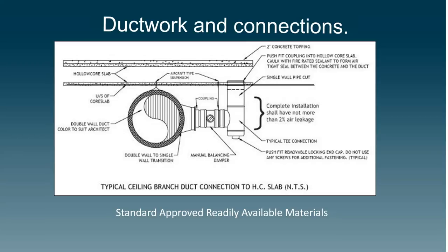Mechanical contractors and sheet metal ductwork people don't need to retool themselves — it's standard equipment. The only difference is that the ductwork is smaller, and if we use hollow-core slabs we eliminate the need for a lot of branch ductwork, so installation becomes much cleaner. Air leakage of 2% on the vertical branch duct does not exceed our limit. We have equipment to test and validate that because it is highly critical for the system to perform as intended.